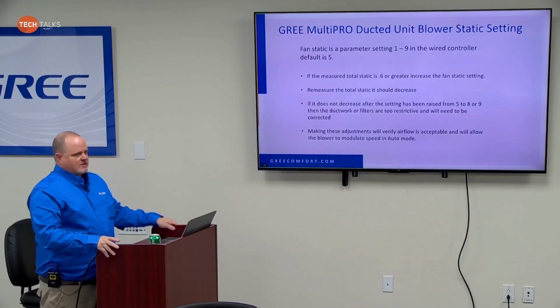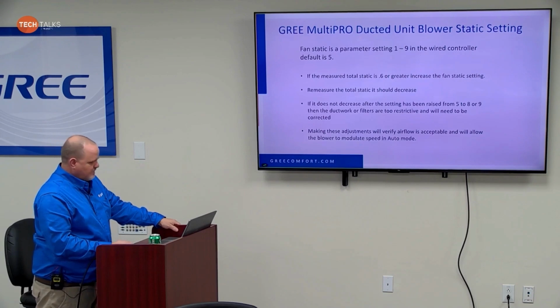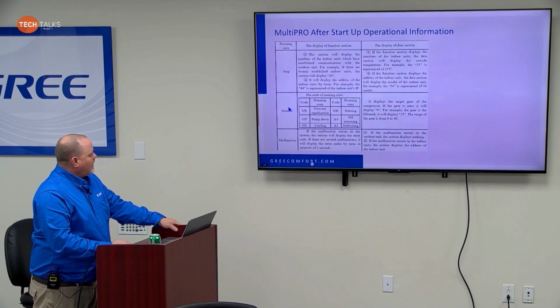So now the way the MultiPRO air handler works is it's looking at the inlet and outlet temperature sensors on that coil. So when the fan's on auto, it'll adjust the blower speed. But if you crank that thing all the way up to the highest torque setting and you don't have any kind of high static, it's never going to modulate down. So if the blower's not modulating at all, that's the complaint. They put it on auto and it always runs at the same fan speed. It's because your controller's not set up right, or you got too high static pressure drop across your air handler. Okay? All right, moving on.